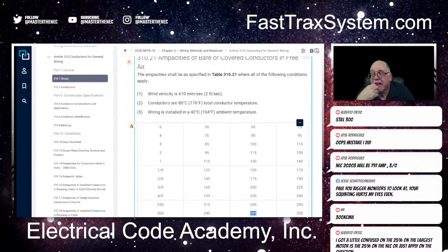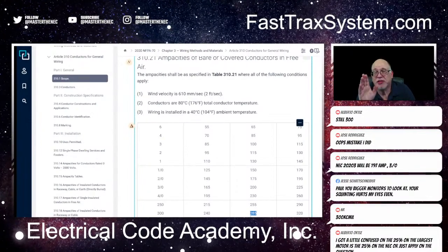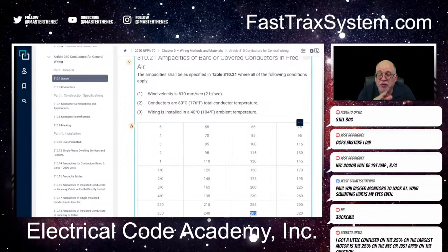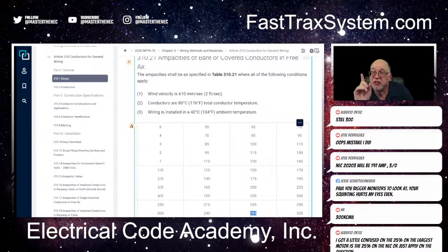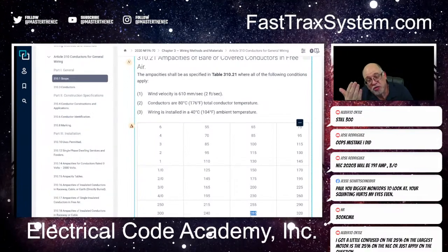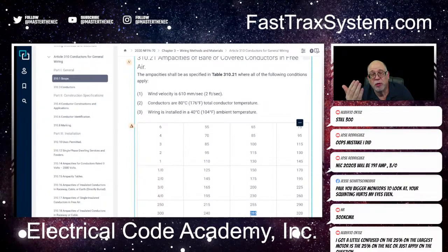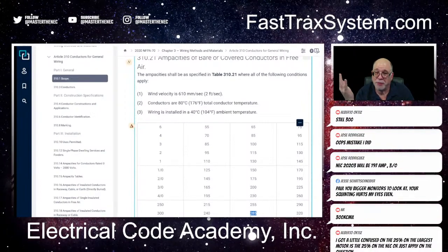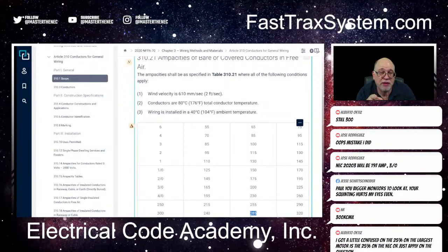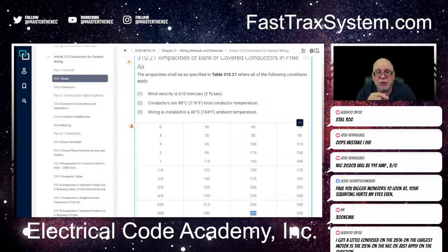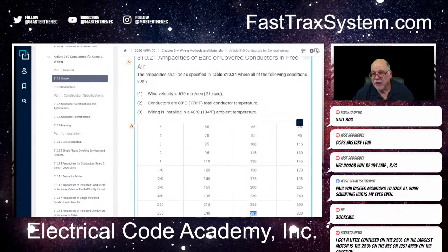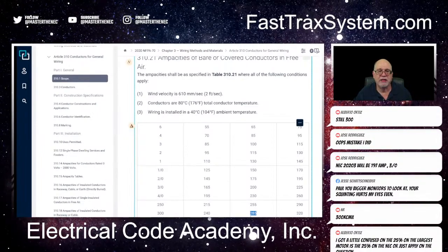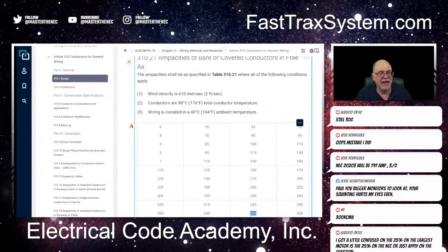But anyway, great example. But just remember, in 2020, you can apply the 70% to the ranges and dryers in the standard method, but in the 2023, you get to apply both of those for the neutral reduction. It's a beautiful thing, okay? That's good trivia tomorrow at work. Ask people, do they know that, okay? All right, anyway, so in our case, we got our answers. We answered 19 through 22. Hopefully you got something out of that.